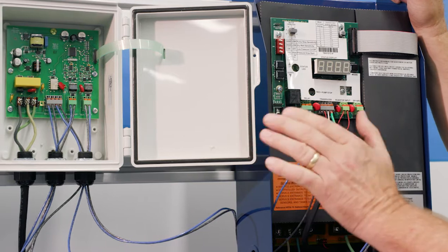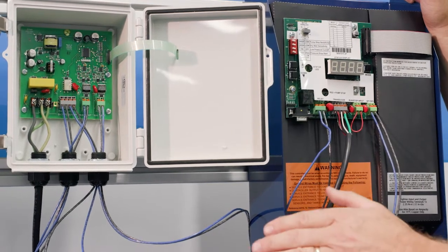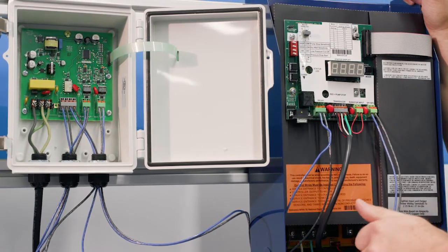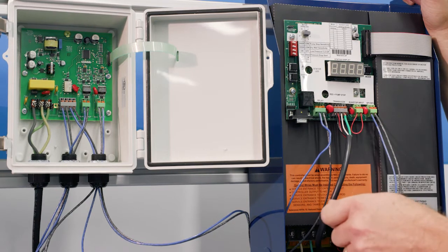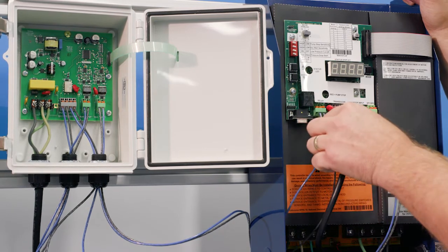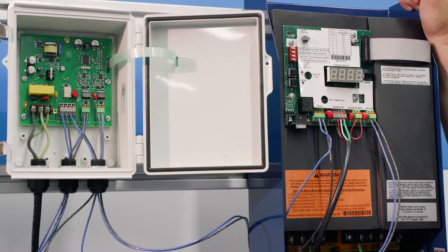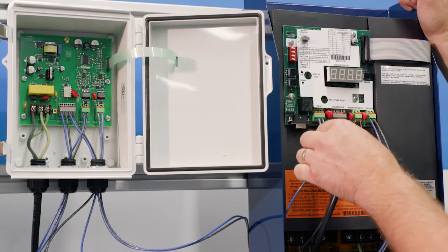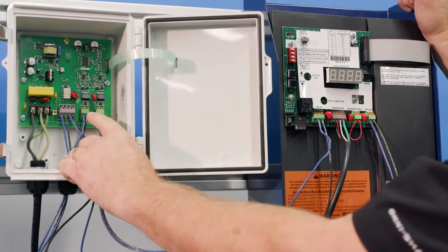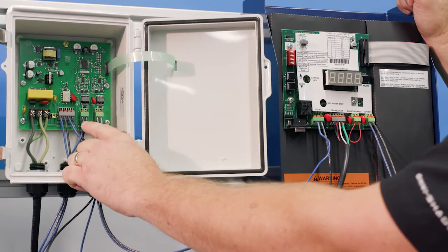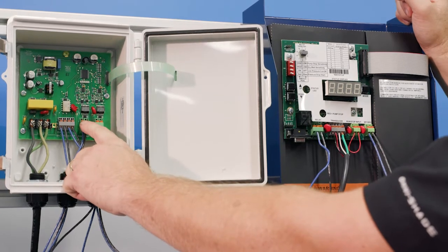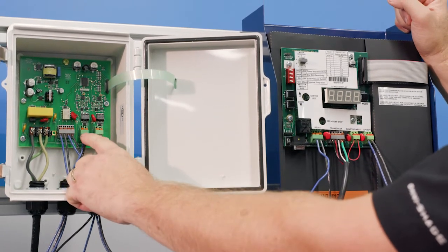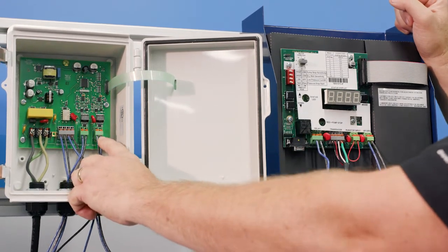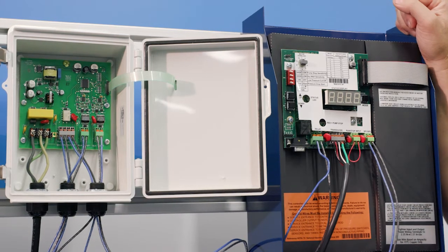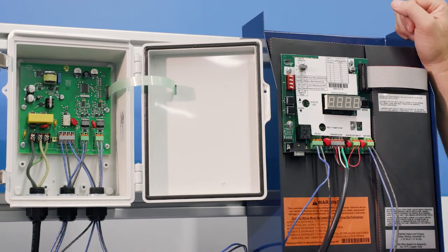So, we have to sort of figure that out before we do the wiring. Do we want our lead lag alternation based on runtime? Then we're going to be connected to the relay. Or if we want it on elapsed time, essentially we don't wire to the relay, and these are just simply jumped. So you're going to see a jumper here, connecting these two terminals, and a jumper here. And that is based on elapsed time.